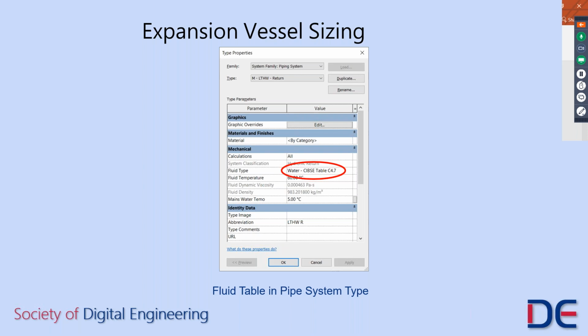Now, when we look at our pipe system type, and we can see here that this is our LTHW return system, we can say this is the fluid type that's going to be bringing in those values from our CIBSE Guide C table. We also need to demonstrate what the temperature is within this return system, and also what the mains water temperature is going to be, because it's the difference between the incoming fluid temperature and the operating fluid temperature that will give us our expansion.